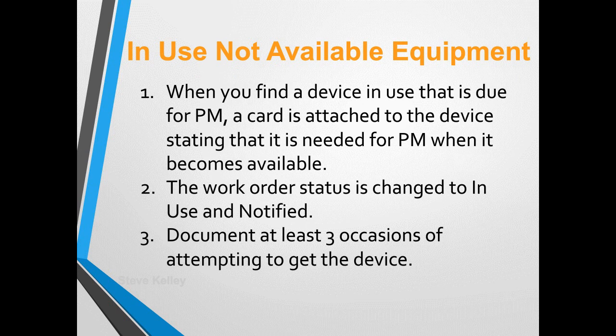So what do we do? When we find a device that's due for PM and it's in use, we attach a card to that device stating it's needed for PM when it becomes available. The work order status is changed to in-use and notified, and we document at least 3 occasions of attempting to get the device.